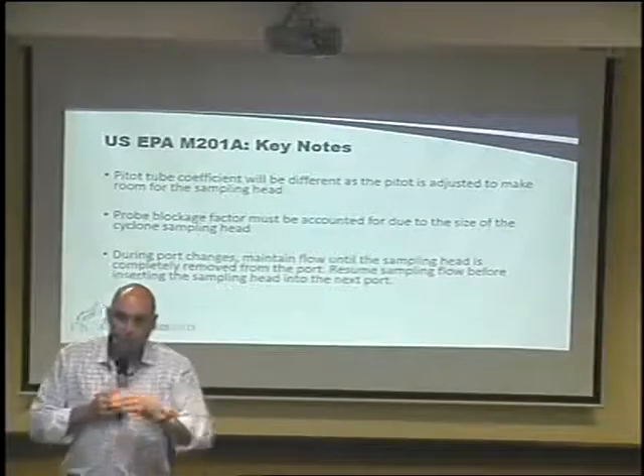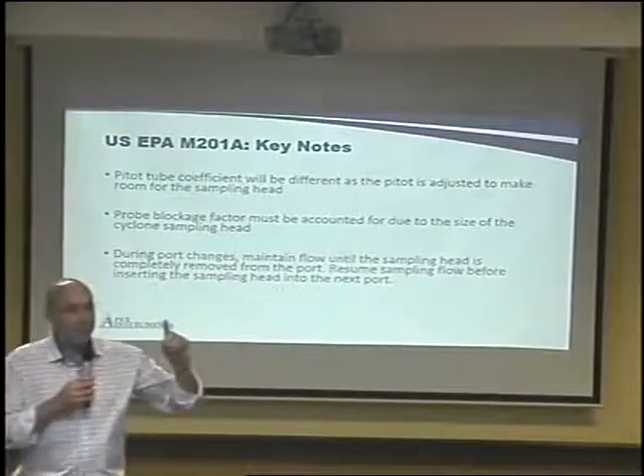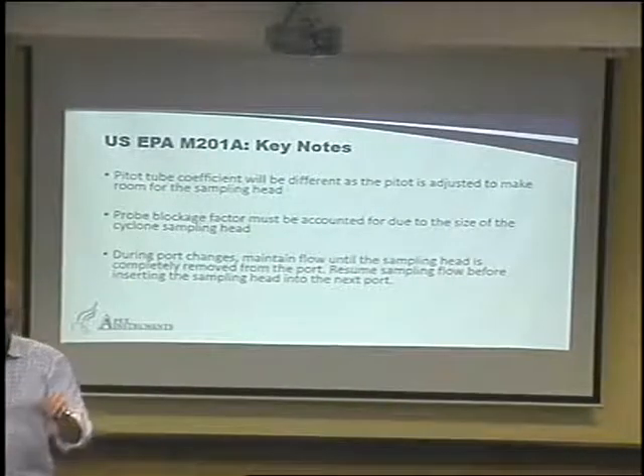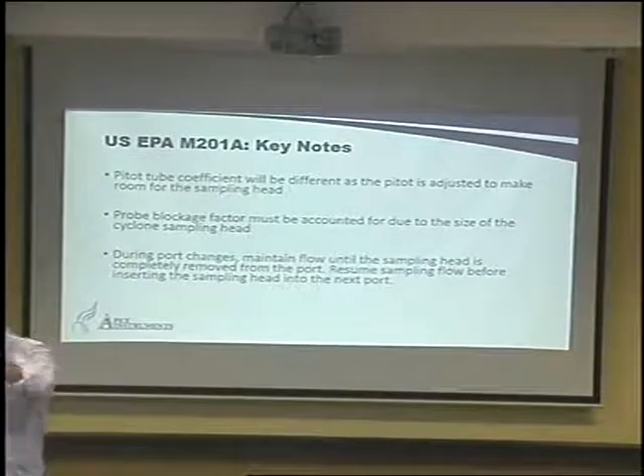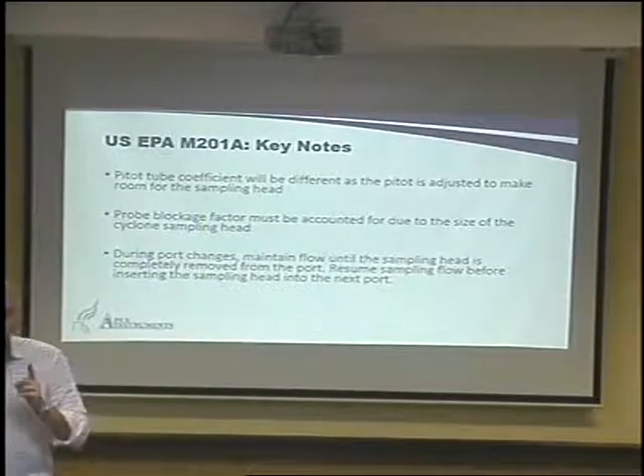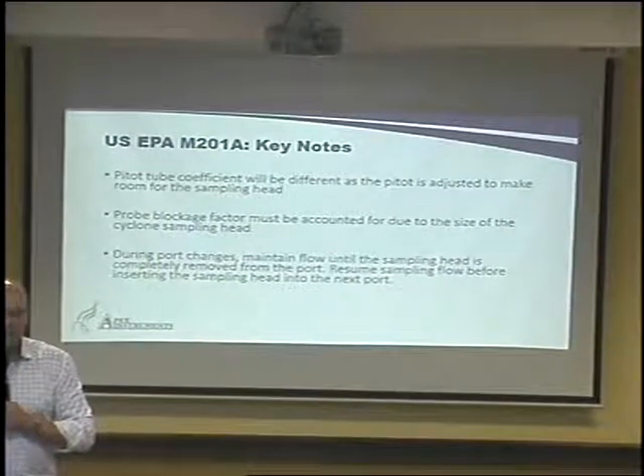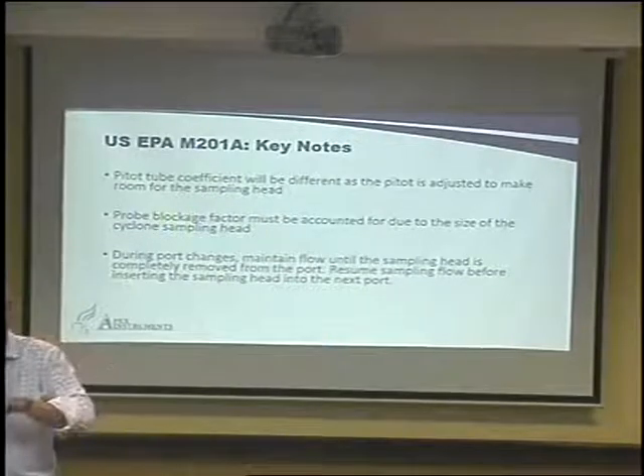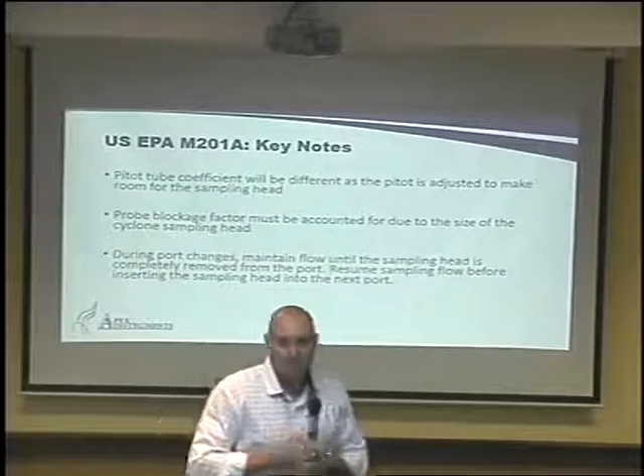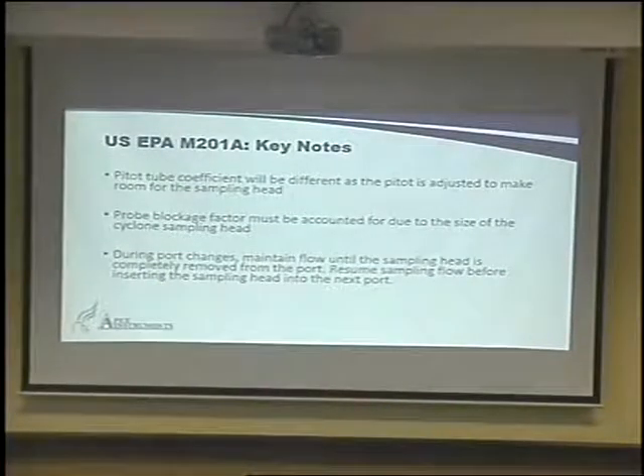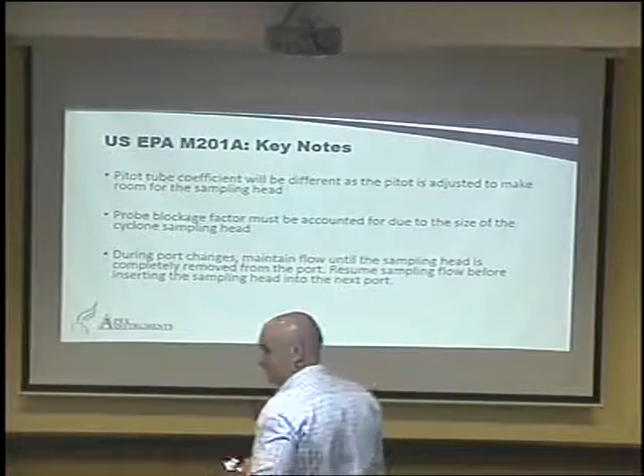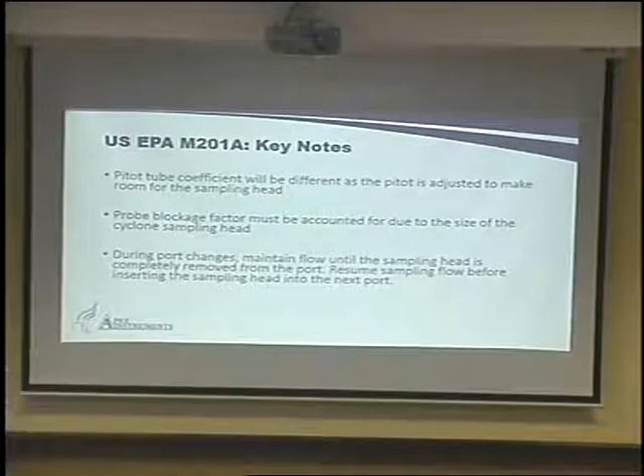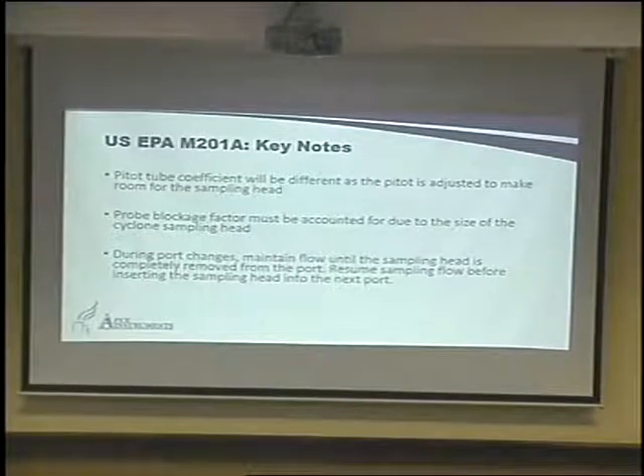But most of the time, the EPA, they're not that. We can do PM1 only, or we can do PM10 and 2.5 together. The single PM, so 10, 2.5, or 1, it's a shorter cyclone. So it has one length of pitot. If you're doing the combination of 10 and 2.5, you need another extra length pitot to be able to do the sampling. So keep in mind, if you're ever interested in purchasing this and using this application for this method, make sure that you're getting the pitot as well with this instrument.